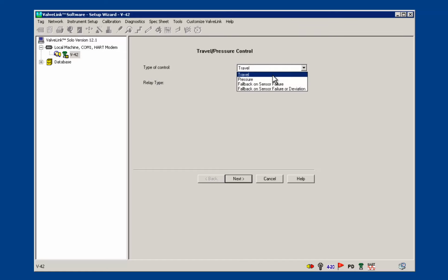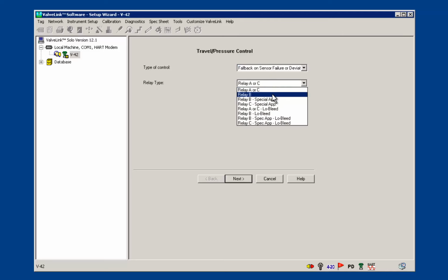The options are travel, pressure, or travel control with fallback options. I'm going to choose fallback on sensor failure or deviation. This option allows the device to default to pressure fallback from travel control. Now we need to choose a relay type. The instrument I am working with has Relay A installed.